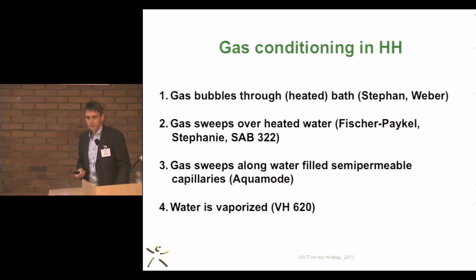So gas conditioning is an important issue because poor gas conditioning might result in airway damaging, and the different heating devices are working differently. And you have either heating devices with gas bubbles through a heated bath, like in the Weber or Stephan heater, or you have gas that sweeps over heated water, like in the Fisher and Paykel or the SAB 322, or there's another one like the Aqua mode, where gas sweeps along water-filled semi-permeable capillaries, which is, I think, no longer available.